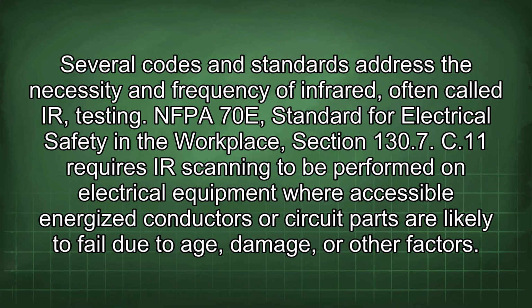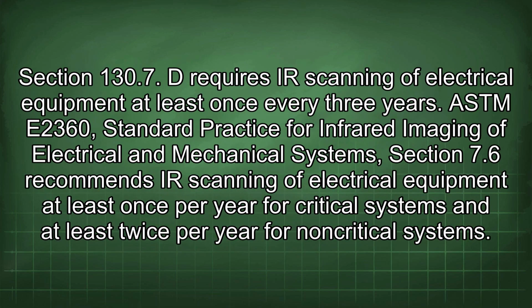Several codes and standards address the necessity and frequency of infrared, often called IR, testing. NFPA 70E, Standard for Electrical Safety in the Workplace, Section 130.7.C.11 requires IR scanning to be performed on electrical equipment where accessible energized conductors or circuit parts are likely to fail due to age, damage, or other factors. Section 130.7.D requires IR scanning of electrical equipment at least once every 3 years.